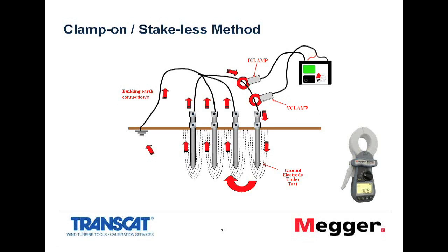We also have the clamp-on stakeless method. Earlier in the presentation, I showed you this clamp meter. We also have a 4-pole instrument, the DET4TCR2, the Mark II version. This instrument can take 2 of these auxiliary clamps using exactly the same method as the clamp meter on the bottom right. Now we've got 2 individual cores, and it's the same method I mentioned earlier, where we induce the current with one clamp and measure how much current is being induced with the other clamp, and from that we can calculate the loop resistance of that circuit. Okay, that's just to give you a background of the other options available.